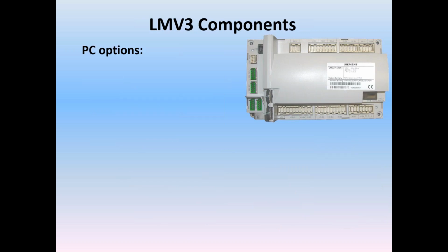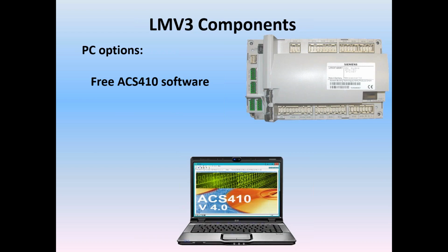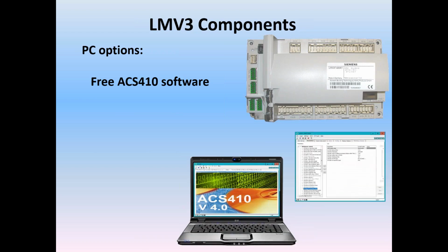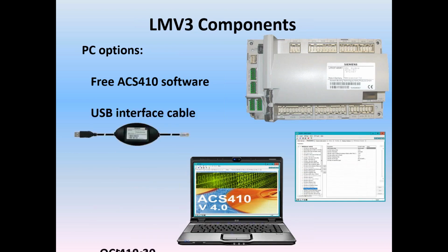The LMV3 can be connected to your personal computer for commissioning. You get free ACS410 software. Put it on your PC. It brings in a commissioning document for reports. You need a USB interface cable. It's called an OCI. An OCI410.30 is a service level where you can add the fuel curves and set up the commissioning of the LMV3.